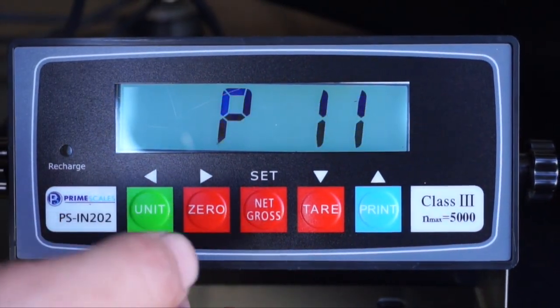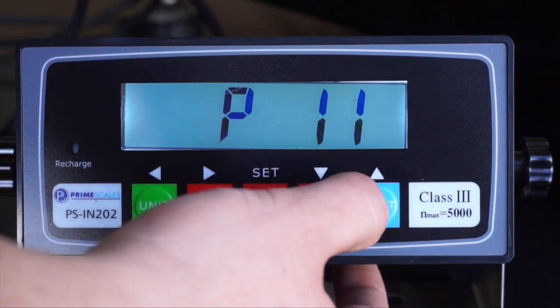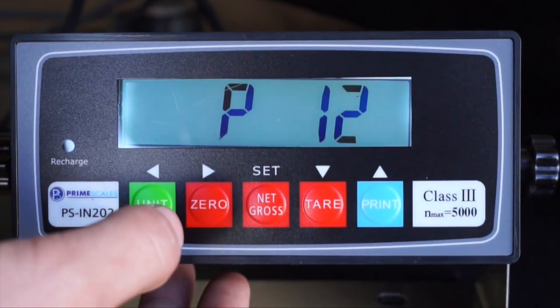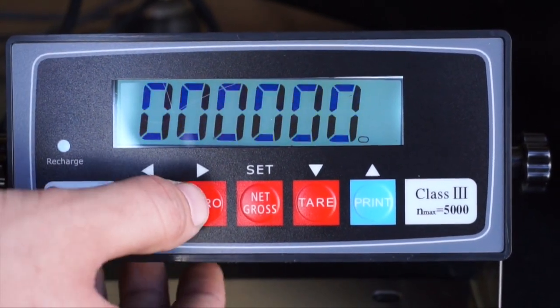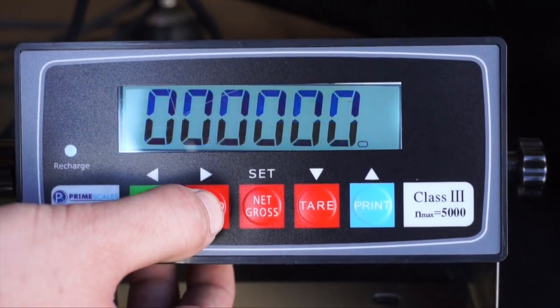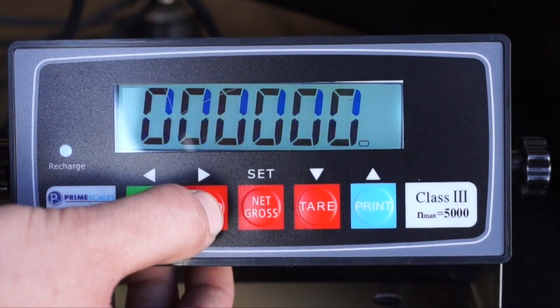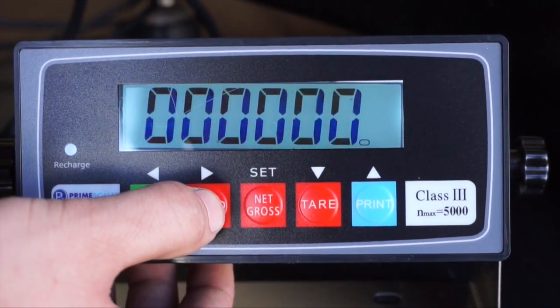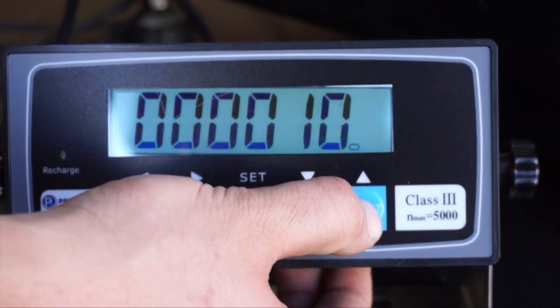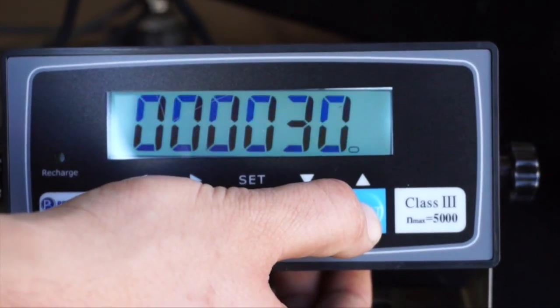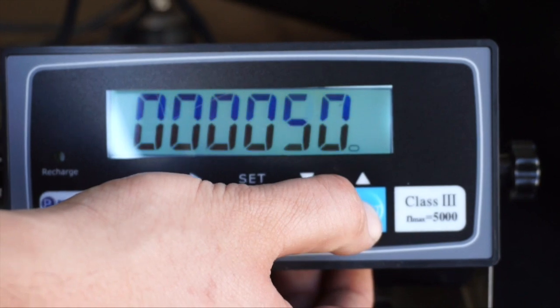Press the print button to move up to P12. Press zero to enter P12. Press zero again to move and set proper weight that we'll calibrate with. Press the print button to move up numbers. We will use 50 pounds for this calibration.